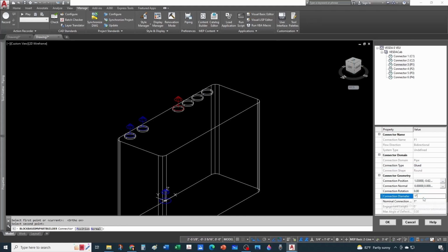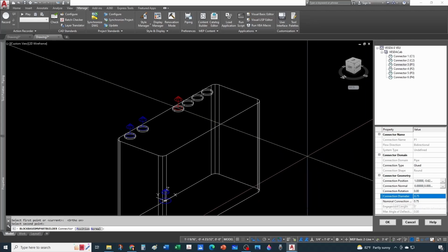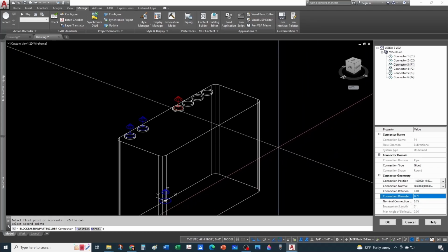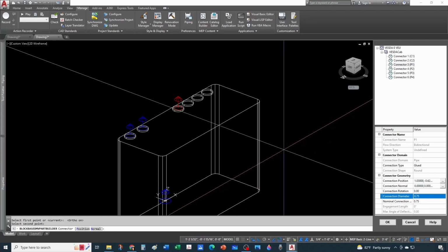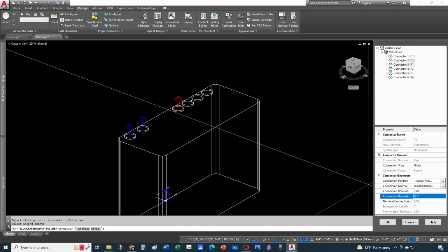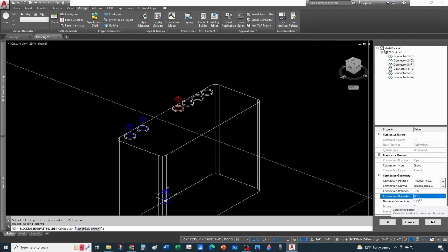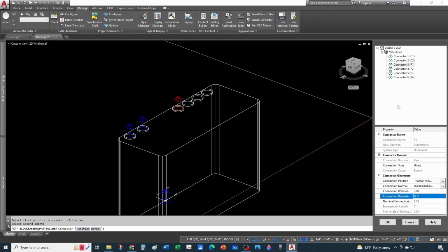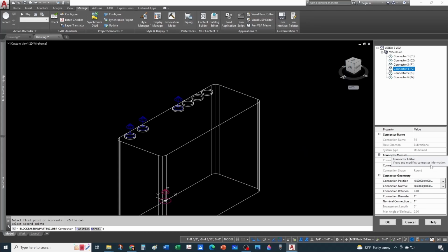and the connection diameter is gonna be 0.75. So it is important that in this drawing, you have a glued pipe type already defined, a routing preference already defined that has this range. Because sometimes if you don't have that, the minimum pipe size could be like 1 inch or something like that, and it wouldn't allow you to change to 0.75. So now we're fine, let's do P2.